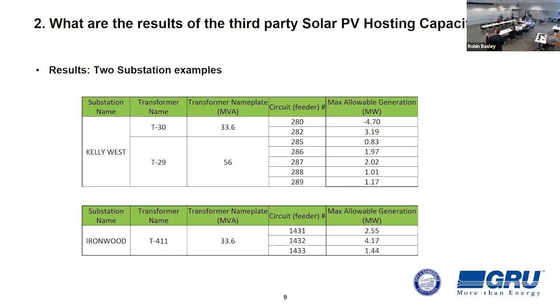Now, you probably noticed the first circuit at the top of the page, circuit number 280, shows a negative number, negative 4.7 megawatts. The reason that's a negative number is because that is actually a backup feeder for our energy center at Shands Hospital. And so it actually has generation interconnected to it. So that's why that's showing a negative number. Okay, the next substation is Ironwood, and it's got one transformer, T411, and it has a total capacity of 33.6 megawatts. And you can see in this scenario, 3 circuits, the minimum amount of solar PV that can be connected to 1433 is 1.44 megawatts, but 1432 can handle up to 4.17 megawatts.